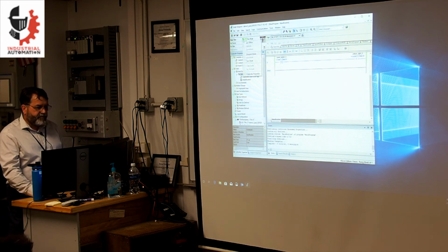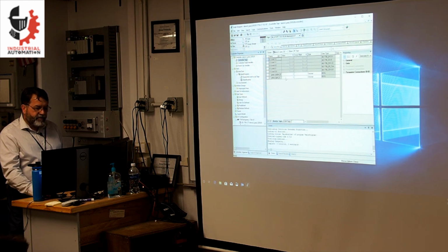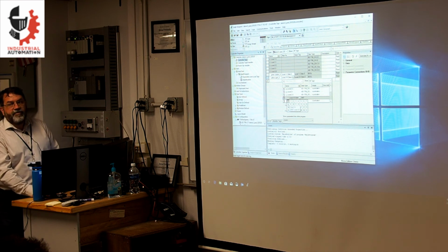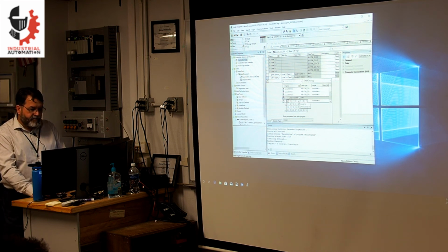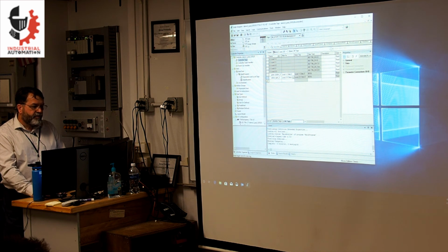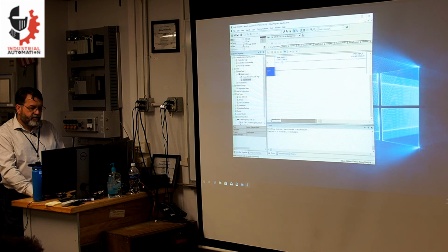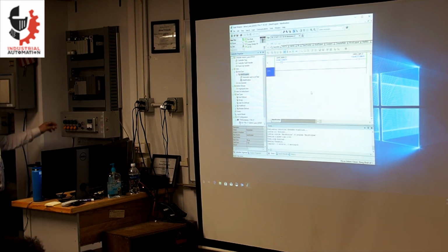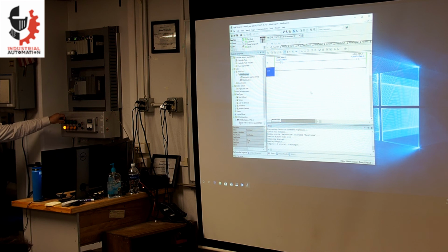So to fix that, I have to go offline, go back to my tags, and edit. And this guy should have been 4. Notice when I go here, it tells me that 0 is already taken. I'll change that to 4. Check it. I've got no errors. Go back online and test it. Now it's working.